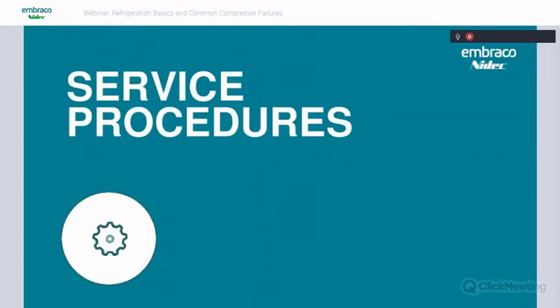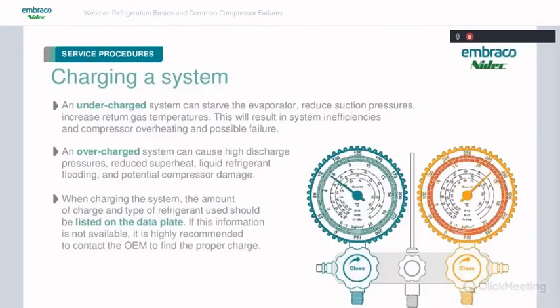So a little bit about some service procedures. When we're charging a system, an undercharged system is going to starve the evaporator, reduce suction pressures, and increase return gas temperatures, which is going to overheat the compressor, and it's going to cause inefficiencies and possibly cause a compressor to fail. And obviously, we're not going to have enough refrigerant in the system to do the job of cooling.